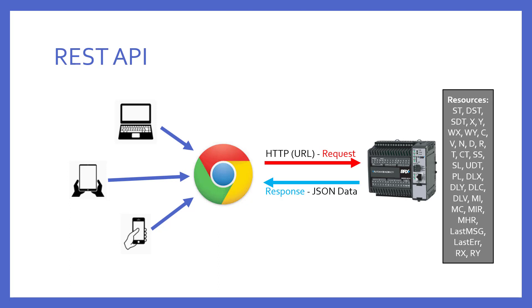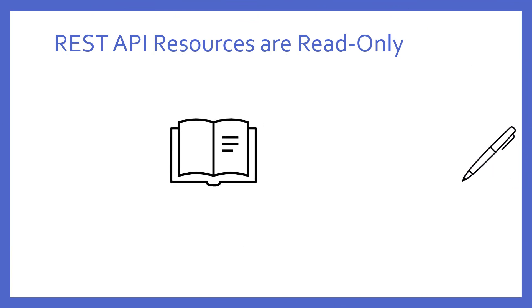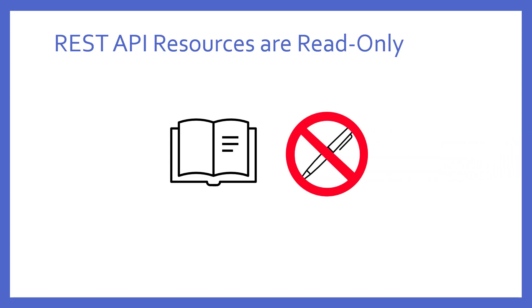The response coming back presents the data requested in the popular JSON data format. The REST API can return the contents of any memory in the PLC. This includes bits, numerics, strings, and even structures. But, how is the URL properly formatted to take advantage of this feature? Before we get into that, it is important to know this feature is for reading only. None of the memory locations can be written to using this feature.